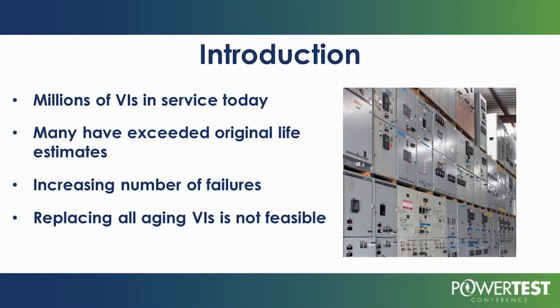There are millions of vacuum interrupters in service today across the world. This is a worldwide product, a worldwide issue. These millions of interrupters are slowly moving towards failure. What is the rate? That can be argued. If you listen to the manufacturers, it's basically never, because they're thinking that the equipment will be replaced before the vacuum interrupters fail. That really hasn't happened.